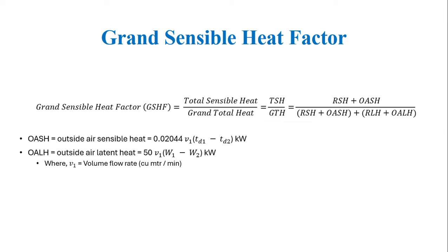The next one is the Grand Sensible Heat Factor, GSHF. Here we consider the outside air heat which is directly added to the room. GSHF is the ratio of total sensible heat divided by grand total heat. The total sensible heat is room sensible heat plus outside air sensible heat, and the total latent heat is room latent heat plus outside air latent heat.